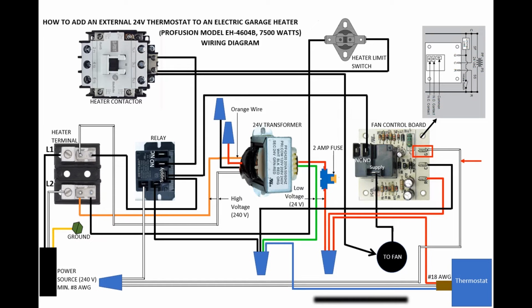So when you apply 24 volts coming from the thermostat to the G terminal, the NO terminal here will now have continuity with the supply voltage, allowing high voltage current to flow from the supply terminal to the fan motor by this black wire, turning the fan motor on.